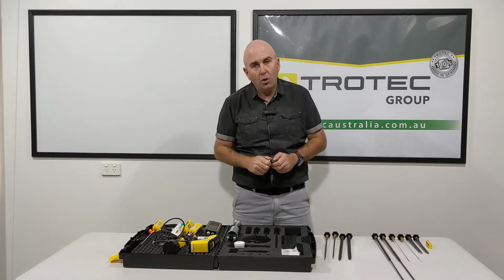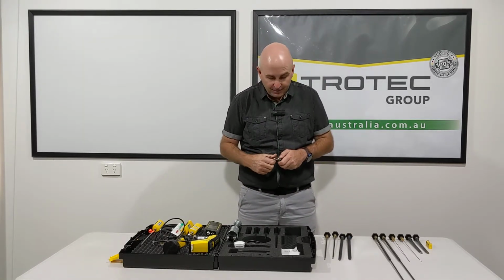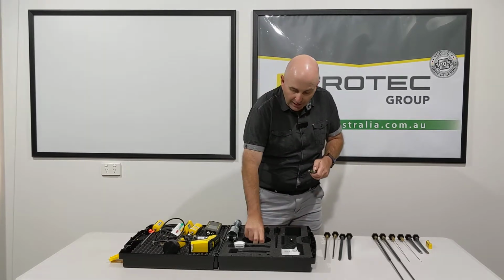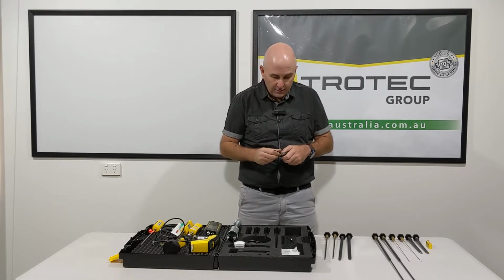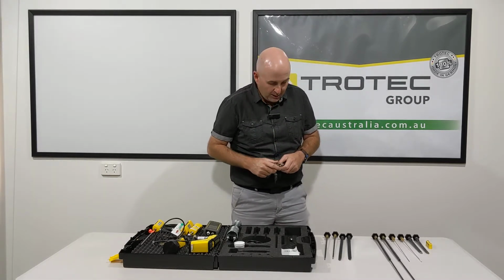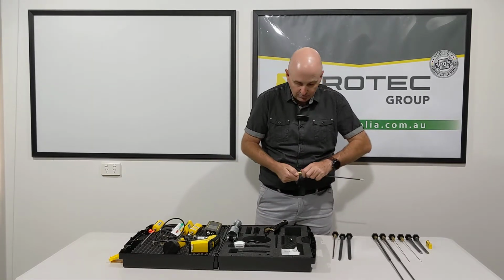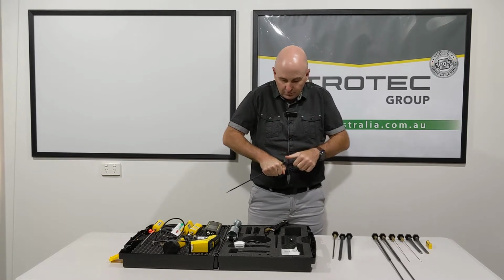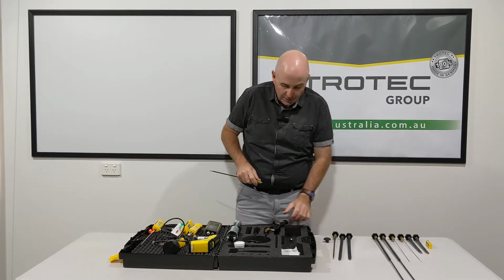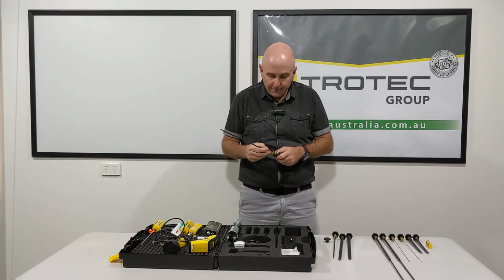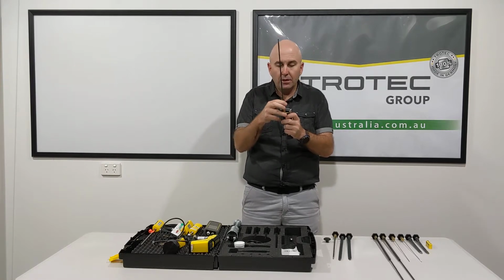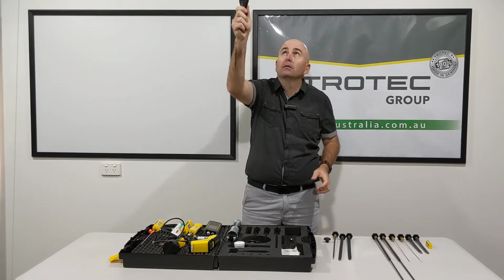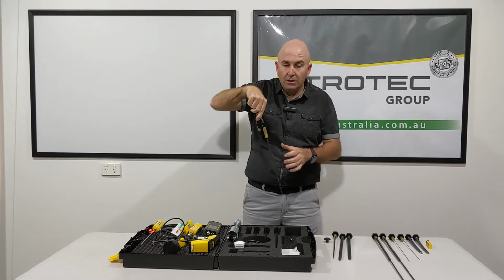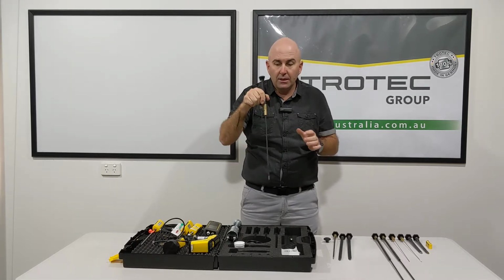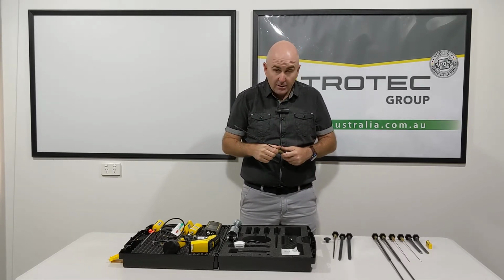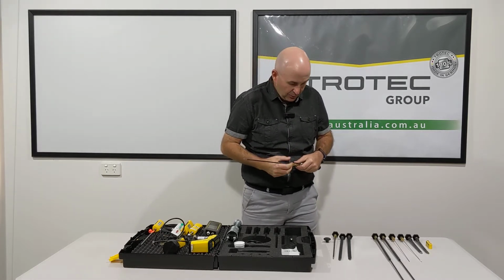Fantastic. What you can also do with your actual pin probe is undo, and we have our little brass connection here that we can screw on the end. And with that, we undo our insulated rod, pop it on the end here, and now we can put two together and start to check up higher, or under floor, under kitchens and so forth. So we've got an added advantage of putting this together with a handheld pin probe. Great way to do that. Unscrew this, we'll pop it down here.